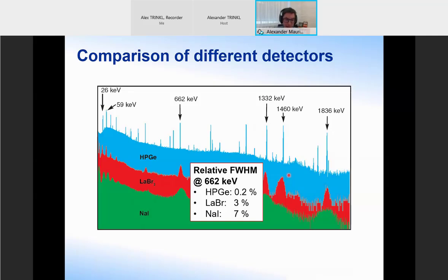And if you look at the peak at 662 keV, at the relative full width half max, so what is the width of the peak compared to its energy? We'll see that for high purity germanium, it's around 0.2%. So the full width at half max is around 1.5 kilo electron volt. For lanthanum bromide, it's around 3%. And for sodium iodide, it's around 7%. So that is quite drastically different values, and that's why the peak is so much wider on the scintillation type detectors as on the high purity germanium detector.